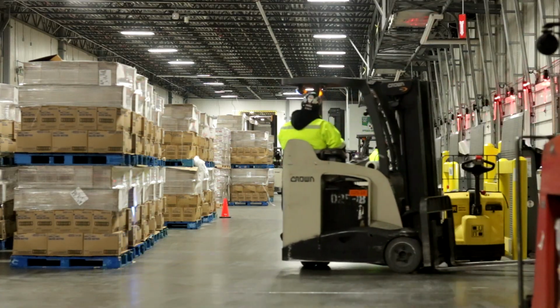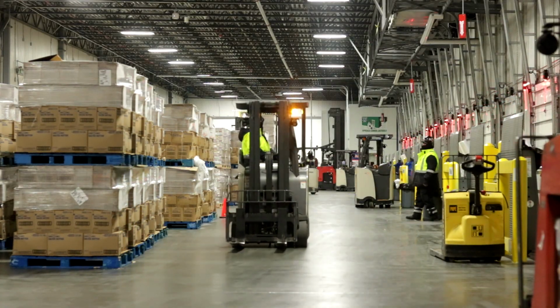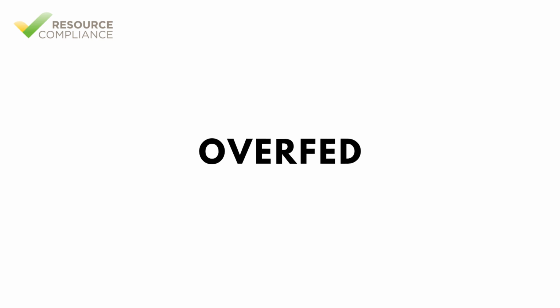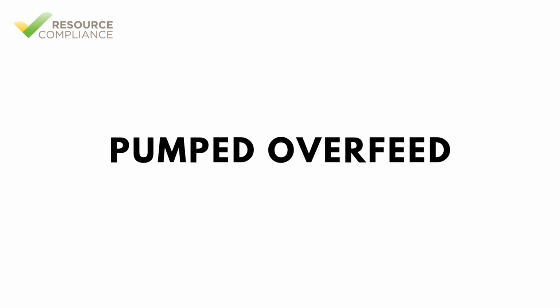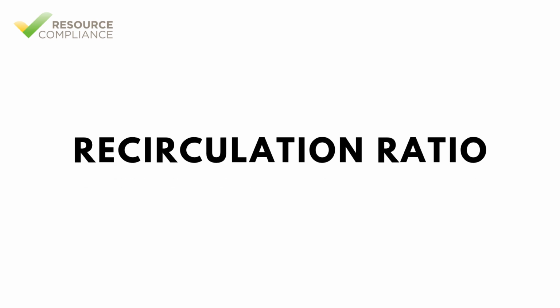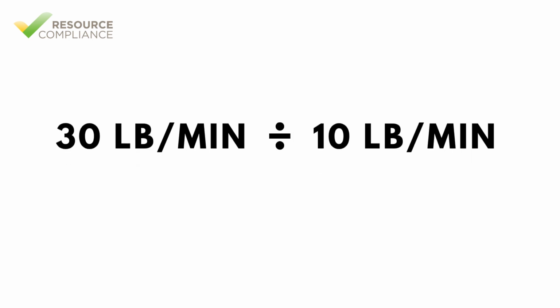A recirculator pump will typically supply more liquid than will boil in the evaporators. When this is the case, the evaporators are said to be overfed, and this method of supplying evaporators is rightly called pumped overfeed. The ratio of the liquid fed by the pump to the amount of vapor formed in the evaporators is referred to as the recirculation ratio. If a pump can move 30 pounds per minute but only 10 pounds per minute of vapor is formed, the recirculation ratio is 30 divided by 10, or 3 to 1.